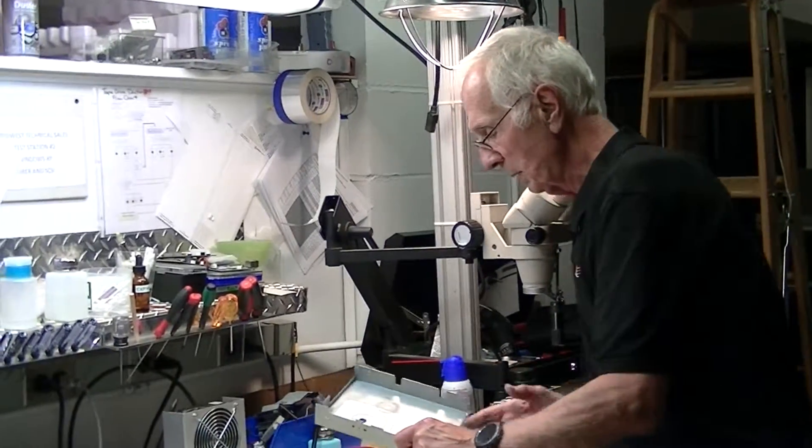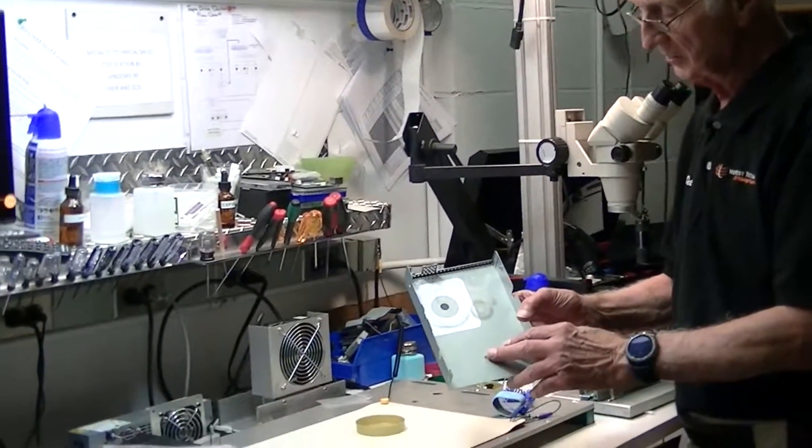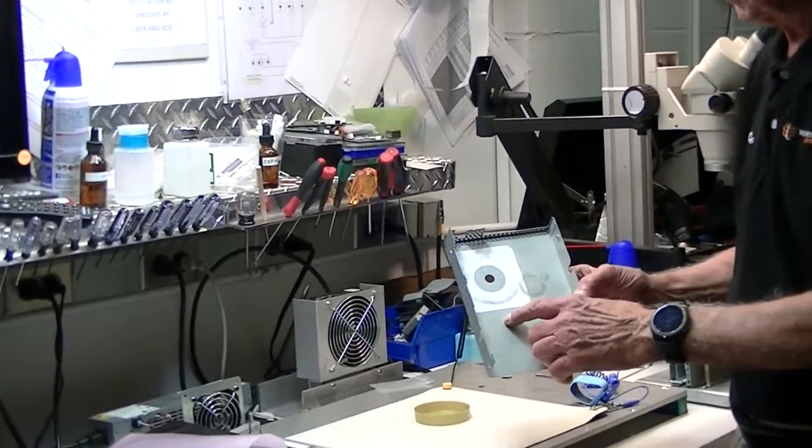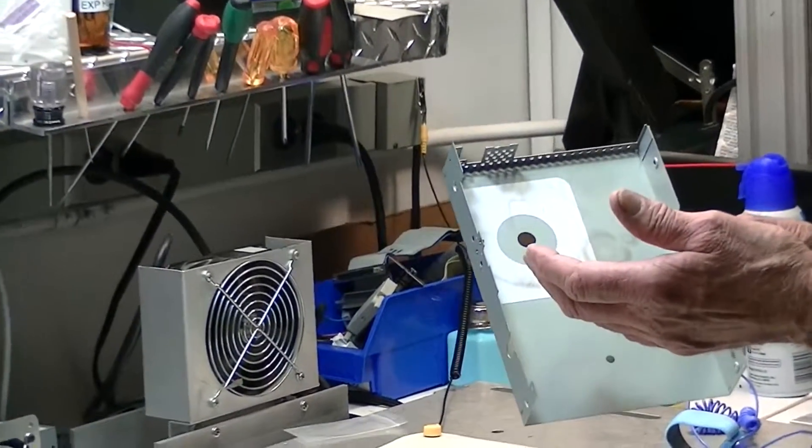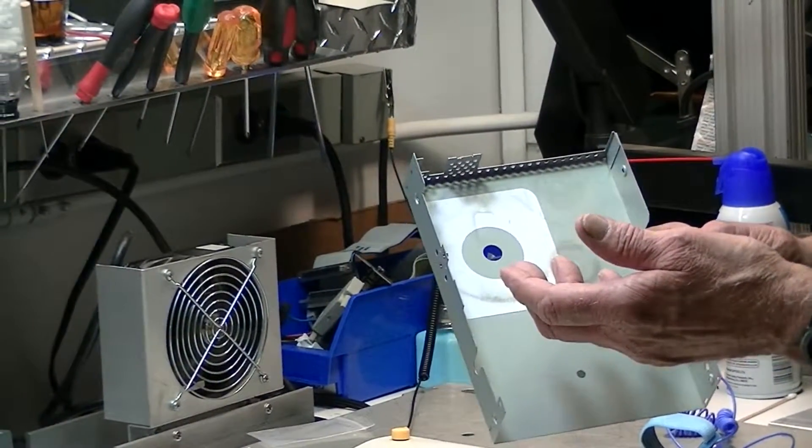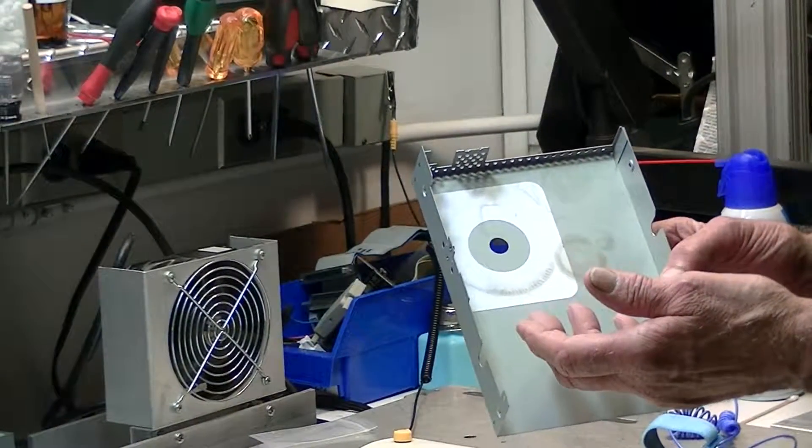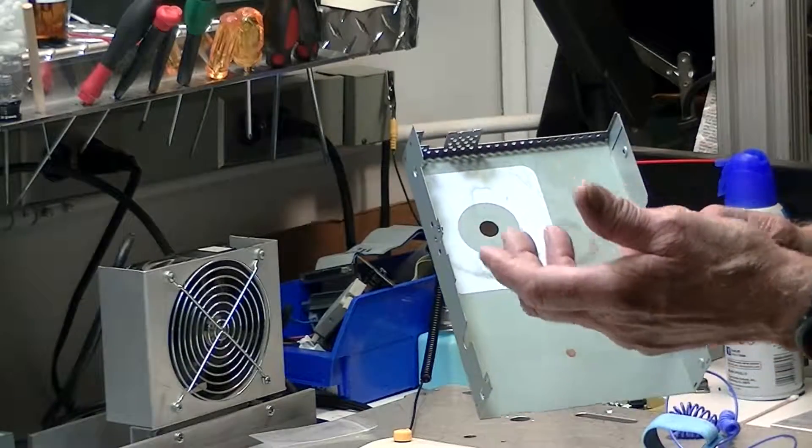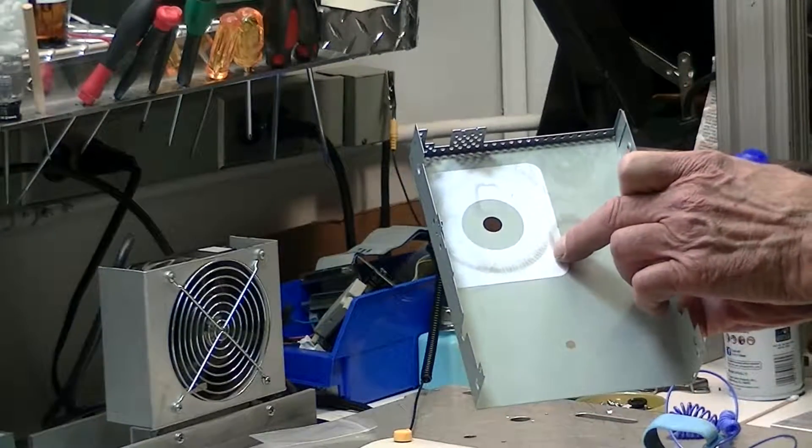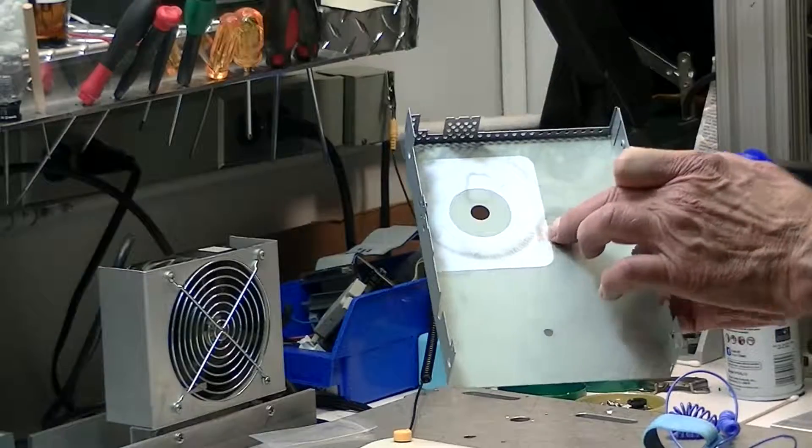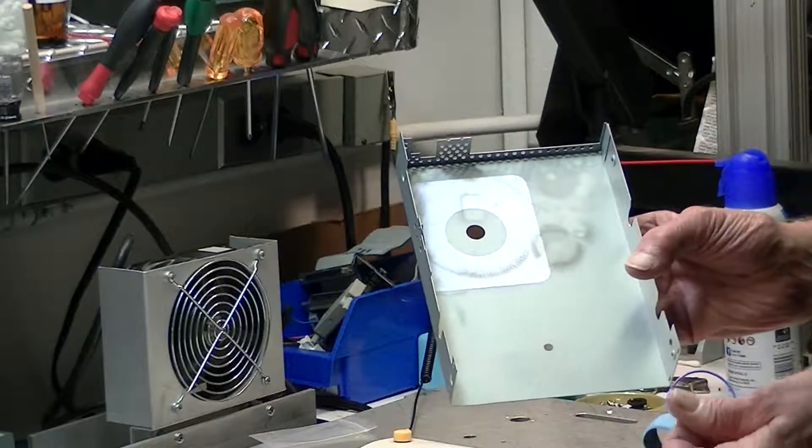So when we pull this apart, you can see debris buildup. And this debris has been peeled off the surface of the media because he didn't use IBM media. It's deposited here. And you can see with my finger, it's dirty.